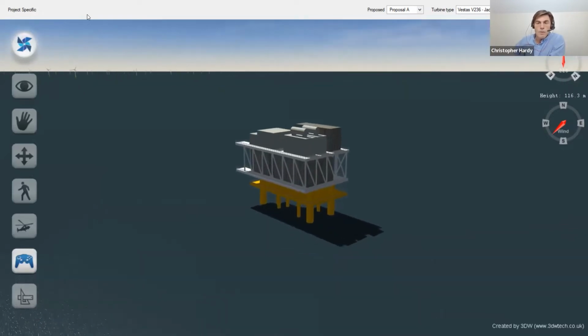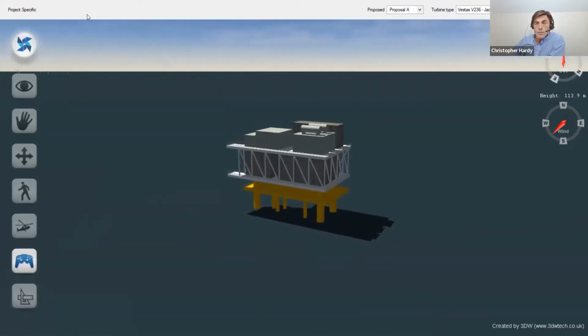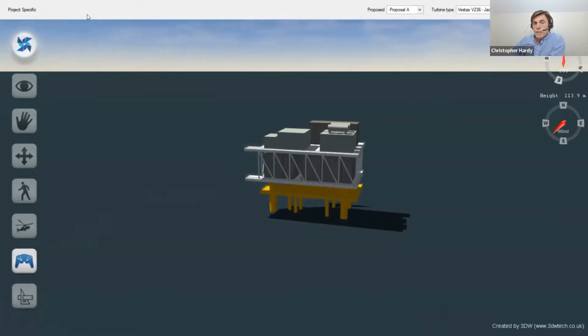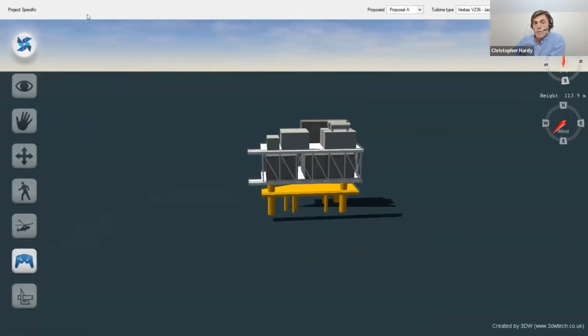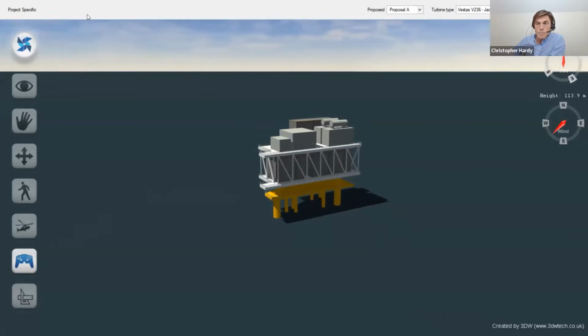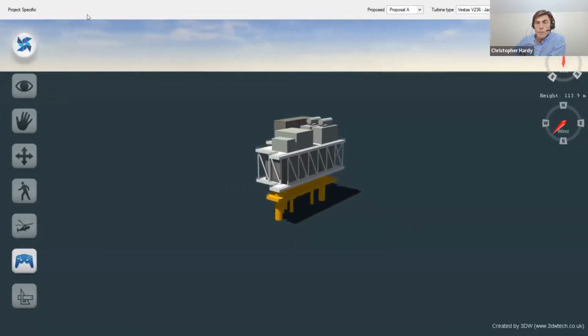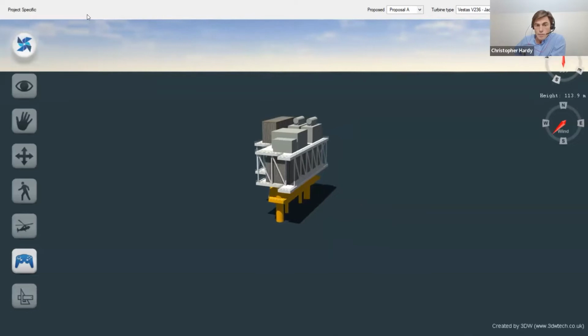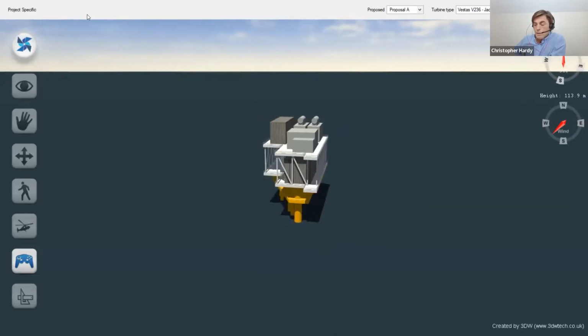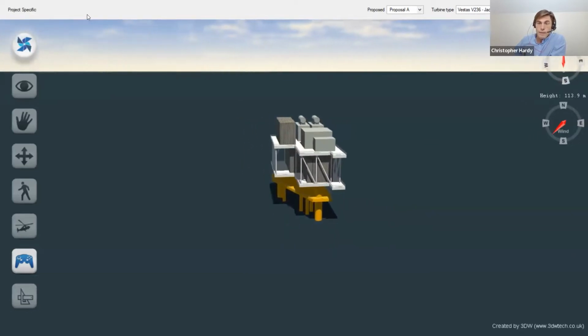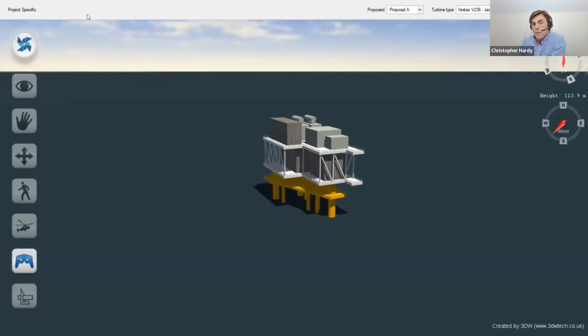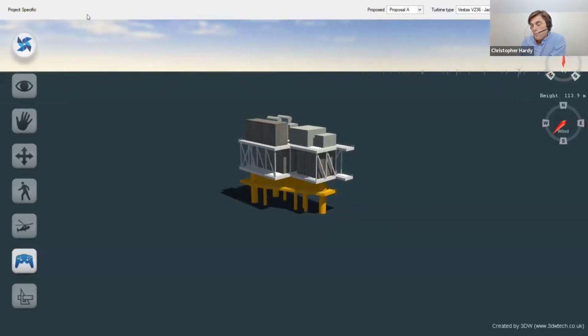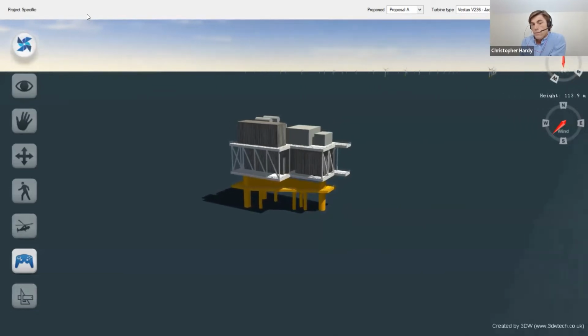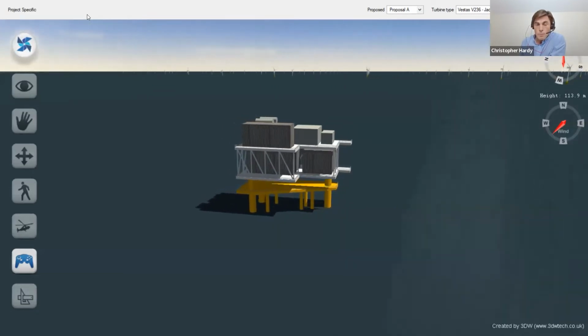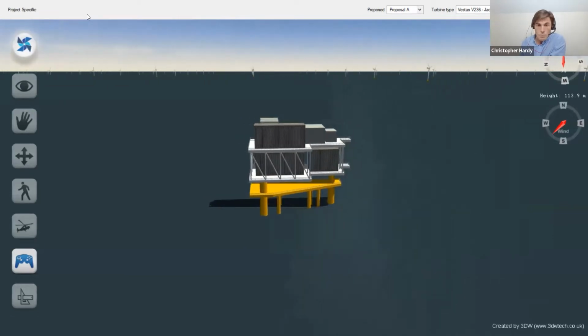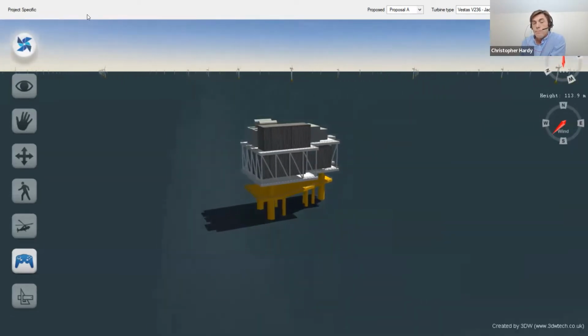The platform serves several critical functions. It's first the collection and termination point for the inter-array cable system that connects each individual turbine to each other and then to the platform, operating at a voltage of up to 69 kilovolts. The offshore substation then steps up the voltage to 275 to 345 kilovolts for export to the onshore substation.